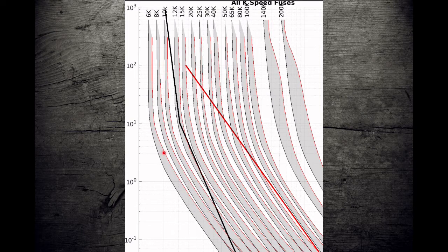Remember, if we're on this side of the inrush line, it's assumed no fault is present and everything is working as intended. So for our fuse to operate here would be considered a nuisance trip and a protection failure. You don't want to be putting your customers in the dark for no good reason.